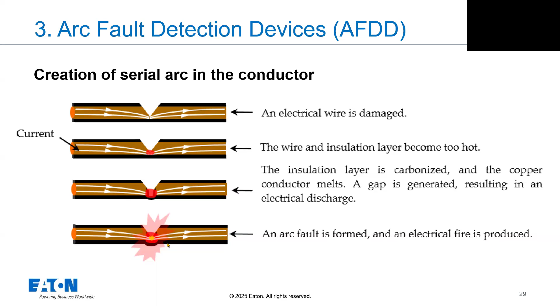If there's a weak point in the installation, like an almost cut conductor or a poor connection in a terminal, the situation develops: at some point the connection becomes disconnected, and an arc is created at that point. If the arc persists for a longer time, carbonization of the insulation starts, and eventually fire can result. This is the reason for this discussion.